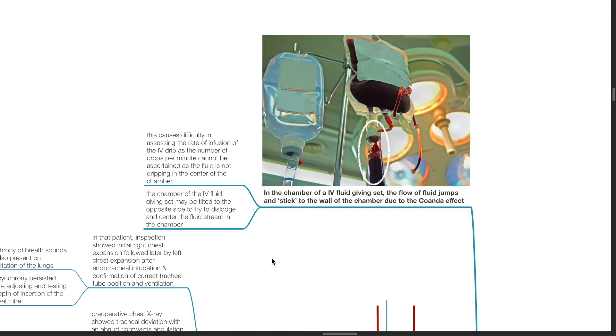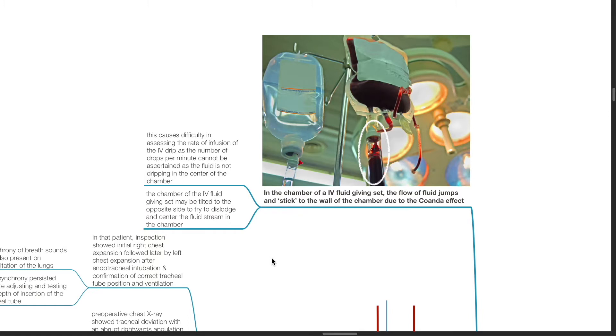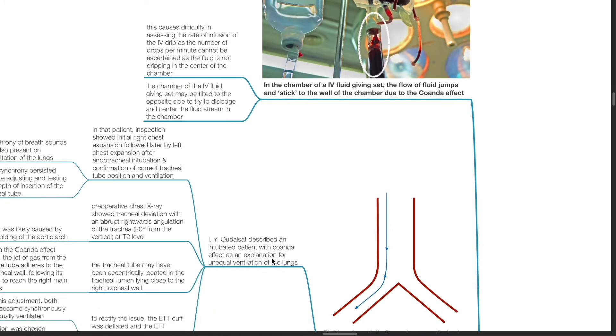This causes difficulty in assessing the rate of infusion of the IV drip as the number of drops per minute cannot be ascertained as the fluid is not dripping in the centre of the chamber. The chamber of the IV fluid giving set may be tilted to the opposite side to try to dislodge and centre the fluid stream in the chamber.